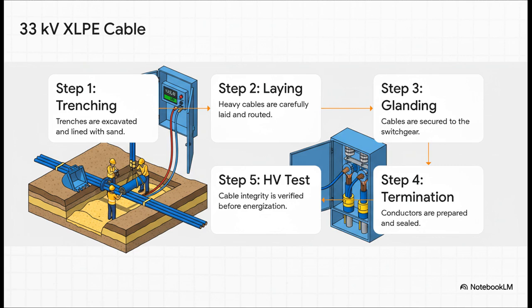And let me tell you, it's a delicate process. You dig trenches, line them with soft sand to protect the cable, and then carefully lay the cable itself. Then comes the really skilled part: securing and sealing them at the switchgear, and then doing the terminations. Once it's all connected, you have to hit it with a high-voltage test to make absolutely sure it's perfect before it ever sees a real load.